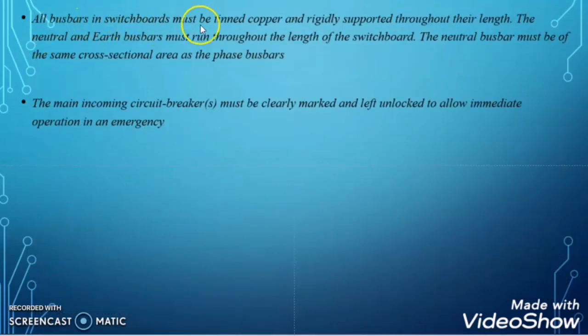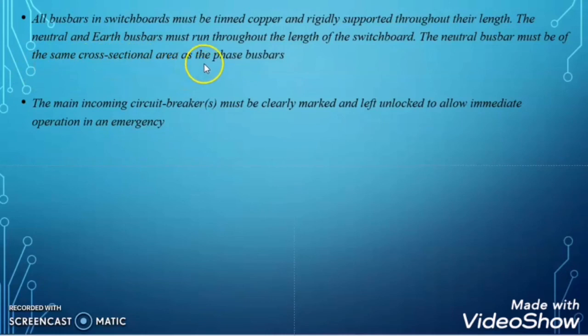The next clause states that all busbars in the switchboard must be tinned copper and rigidly supported throughout their length. The neutral and earth busbars must run throughout the length of the switchboard, and the neutral busbar must be of the same cross-section area as the phase busbars. Finally, the main incoming circuit breaker must be clearly marked and left unlocked to allow immediate operation in an emergency.